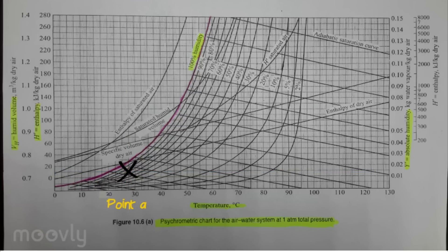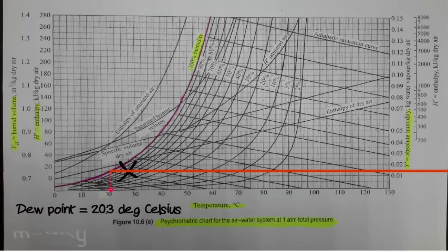Then we determine dew point temperature by moving along the constant humidity line horizontally from point A to the 100% humidity line, and then moving vertically down to the temperature axis. Dew point temperature is around 20.3 degrees Celsius.